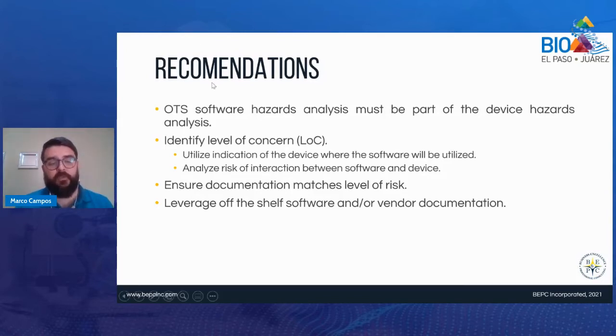The other pointer we'd suggest is that you need to make sure the documentation matches the level of risk. There's such a thing as overkill in the medical device industry, even though it's highly regulated. You have to understand your indication, your use, and then the type of documentation you need to generate.